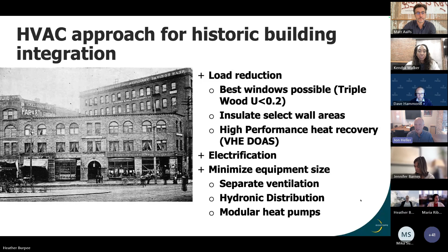Another component of reducing the load was focusing on high efficiency heat recovery to bring the ventilation load down as low as possible. By bringing the load of the building down, we can minimize the size of the HVAC equipment, which was pretty important in this type of historic building because it means smaller ducts, smaller pipes, lighter weight mechanical equipment on the roof, making for easier integration with an old building. Next slide.